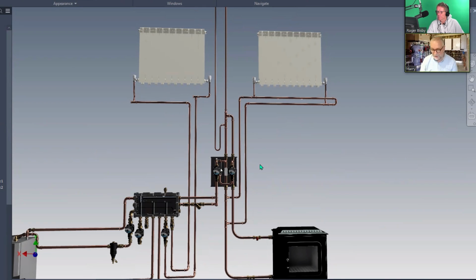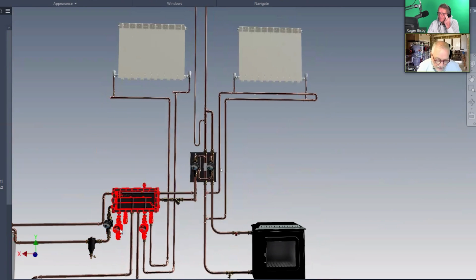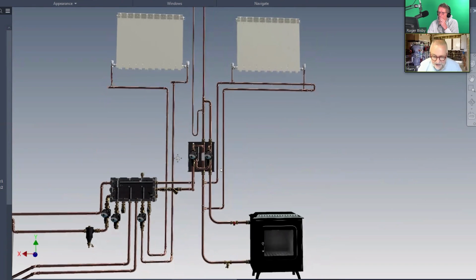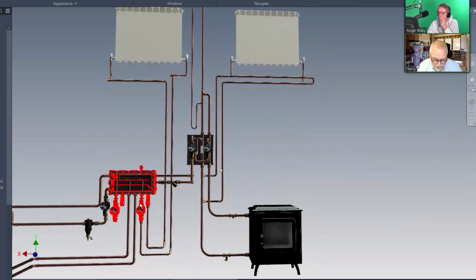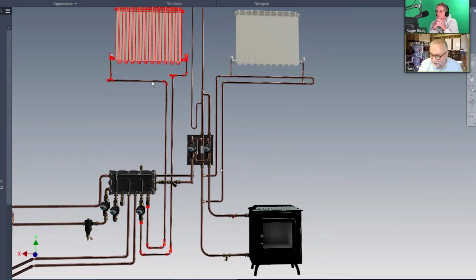Well, where a lot of people make mistakes is, for example, you have a flow and return. If I just forget what's over here, I have a pump here that's actually pumping back to a boiler. But just suppose I'm trying to find the best circuit to look at. Say this one, right? I have a pump here and it's pumping up, and suppose this is going an extended distance. You get people who will put an automatic vent on the flow pipe and a vent on the return pipe. And now the vent on the return is on the suction side of the pump.